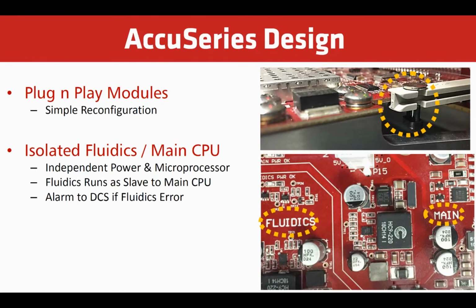The analyzer is made up of modules that plug into a main motherboard in the upper enclosure, so it can be quickly reconfigured. We can actually quickly convert one of these if required from colorimetric to ISE or potentiometric simply by changing an amplifier board. We have isolated the fluidics from the main processing unit above so there's no corrosion, or if anything leaks, it will not get on any of the electronics because it's its own separate enclosure. We alarm to the DCS if indeed there is a fluidics error. If there is no fluidics running, it will trigger an alarm of low sample flow or no sample flow.